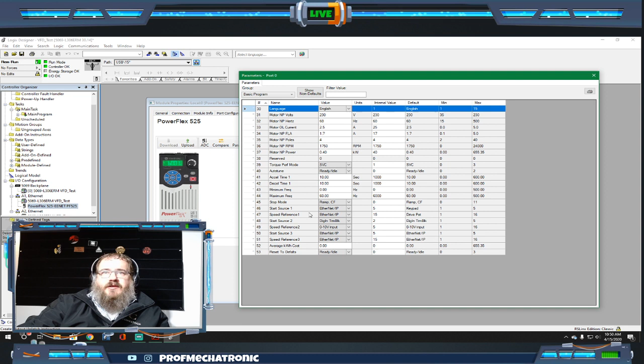Let's look at the basic programming parameters — the basic things I need to set up on a motor to get it to start. Here we can set our motor voltages, motor hertz, overloads, acceleration time for acceleration time 1, start sources, how we're going to start this. These are the basic things you need to set up for your motor. Then it's time to wire the digital inputs and digital outputs — you can set all that up here in the terminals section. As you break down these groups, you're able to see more things in simpler chunks, which allows you to not have to digest a ton of information all at once.